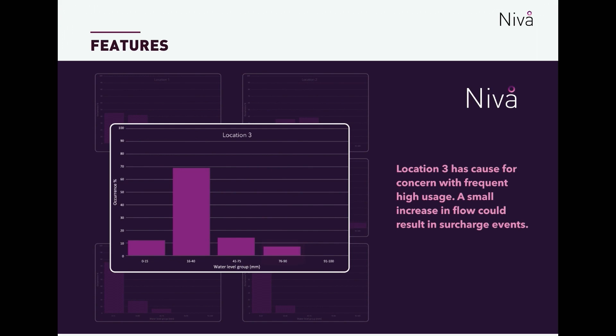But let's pick alarms and alerts. Firstly, alarm thresholds are configurable, not just in absolute level or pipe capacity, but you can also configure how long the exceedance occurs before the system sends an alarm - maybe 5 minutes or 8 hours is more significant for your application. What we're seeing here is capacity levels being bucketed up - there are 5 brackets here, but again you could have 1, 2, 3, 4, 5 brackets depending on your application. The device is able, from the meter head, to produce analytics telling you how long each measurement point spent in that particular bracket. So depending on your application, that might be that the pipe should mostly be empty, or that it should normally run at 10 or 20% full, and you can configure the system to tell you how long it's in each bracket.